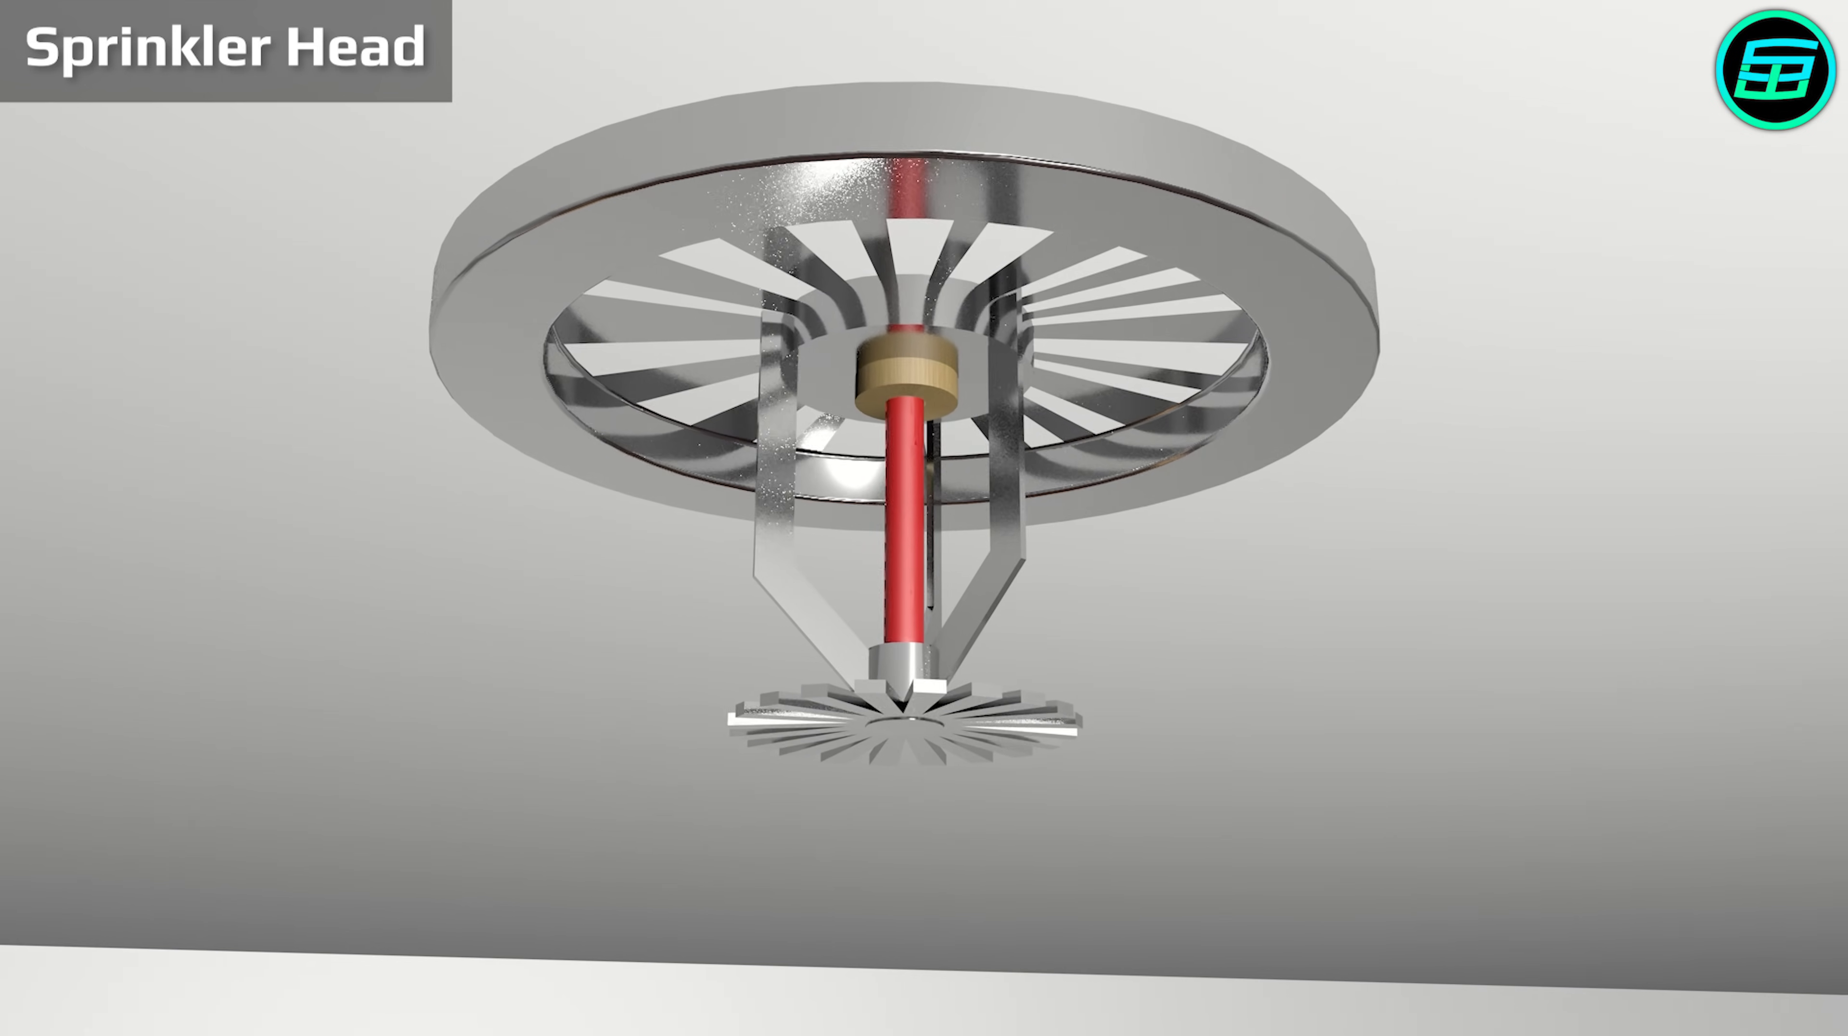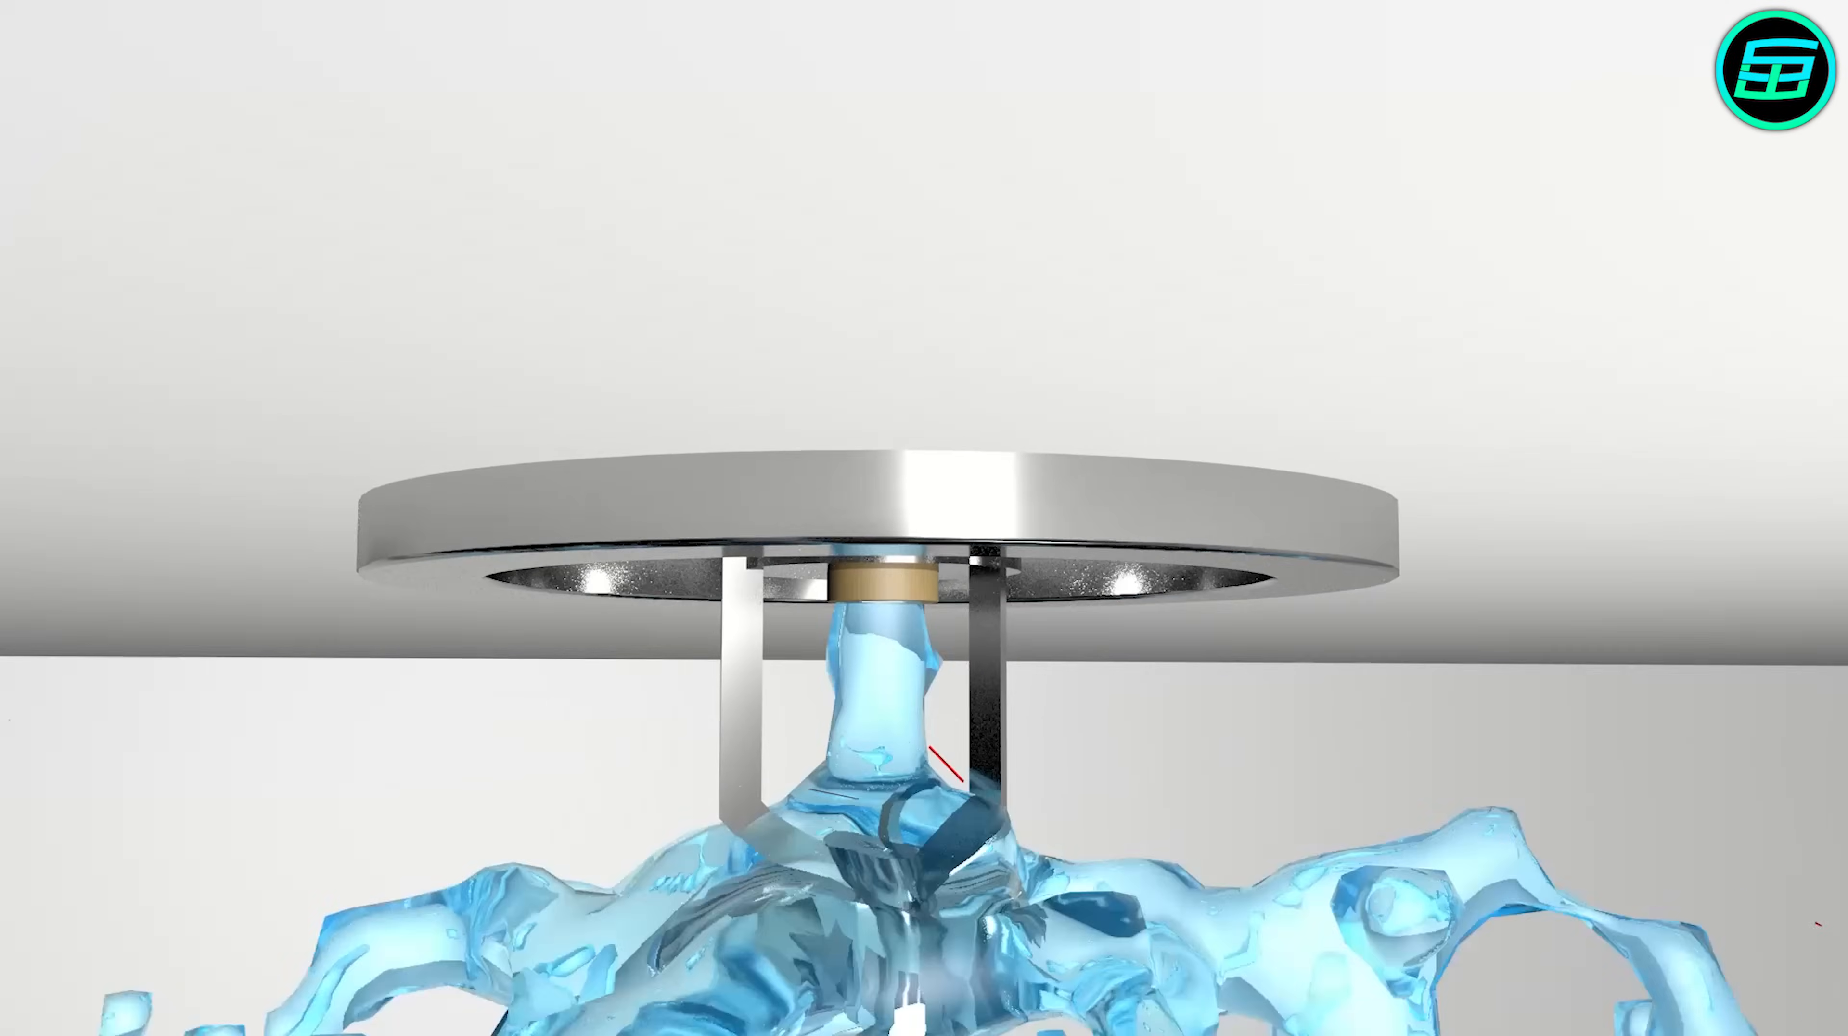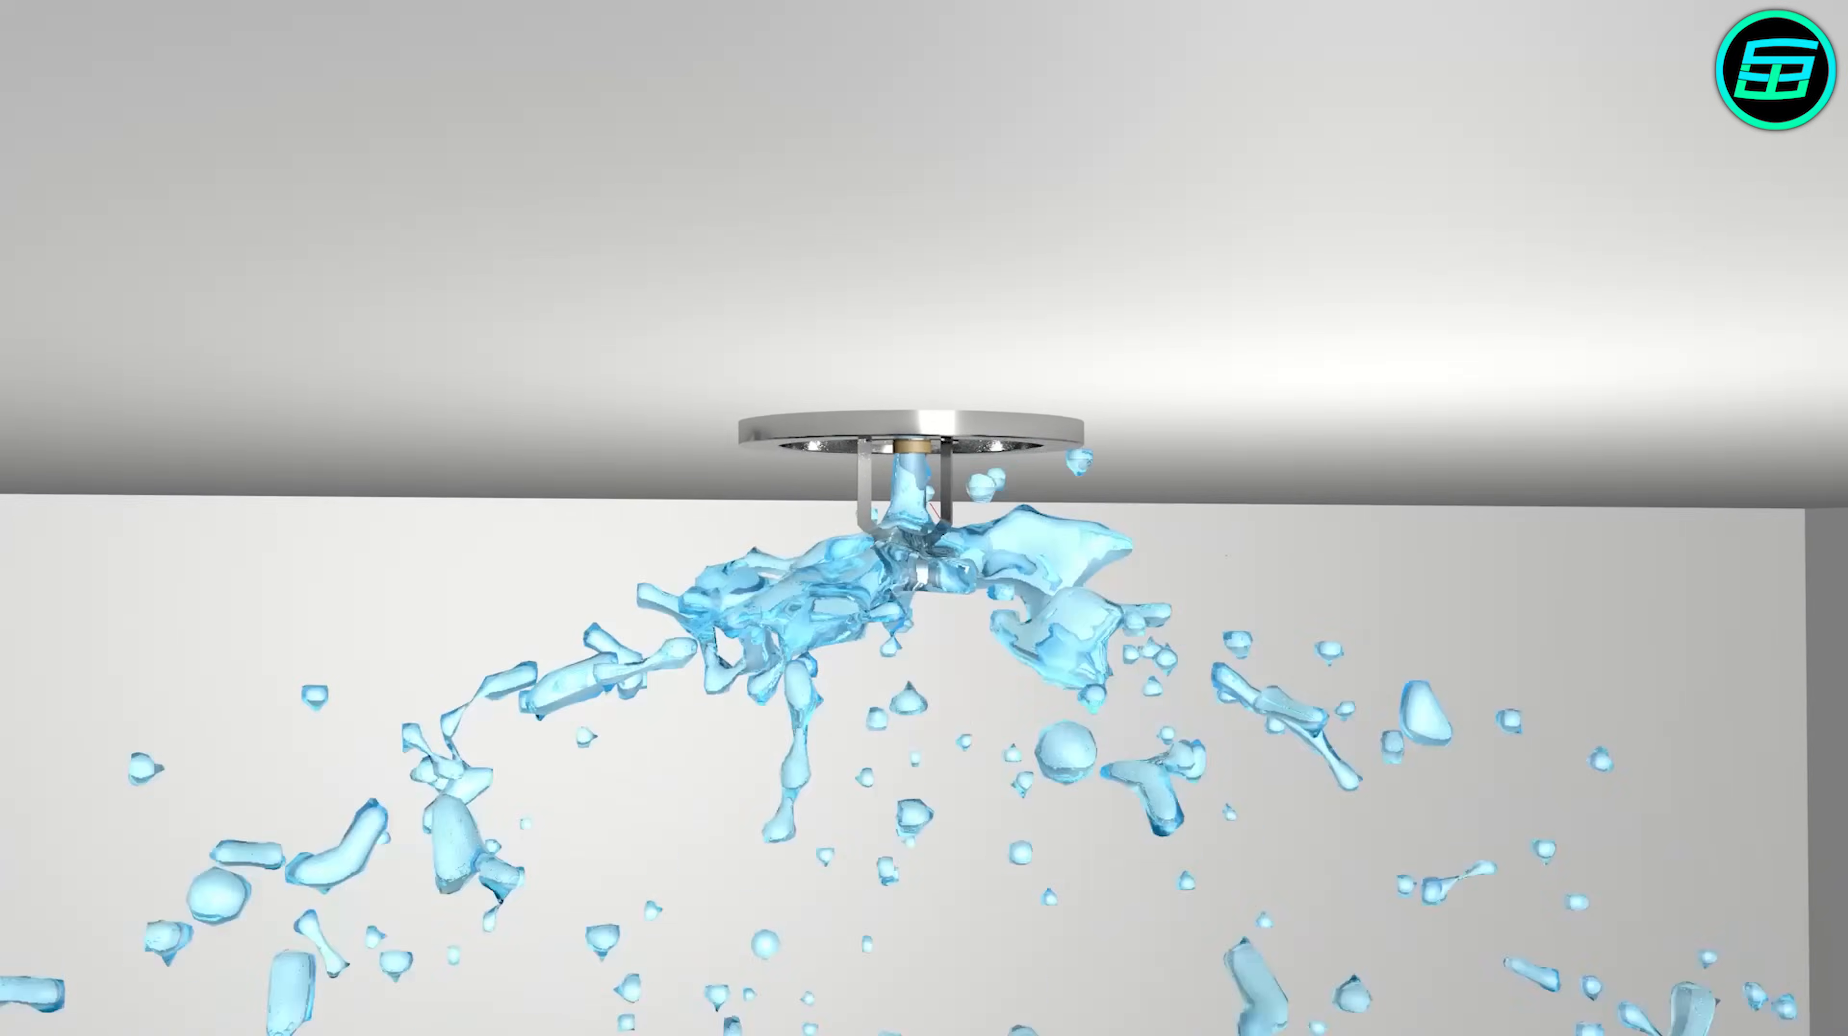When a fire starts, the temperature of the environment rises and the liquid in the glass bulb begins to expand. If the temperature continues to rise, the liquid expands so much that it breaks the glass. There's then nothing left to stop the water and it begins to come out from the plug. When water hits the sprinkler, it's spread over a larger area.